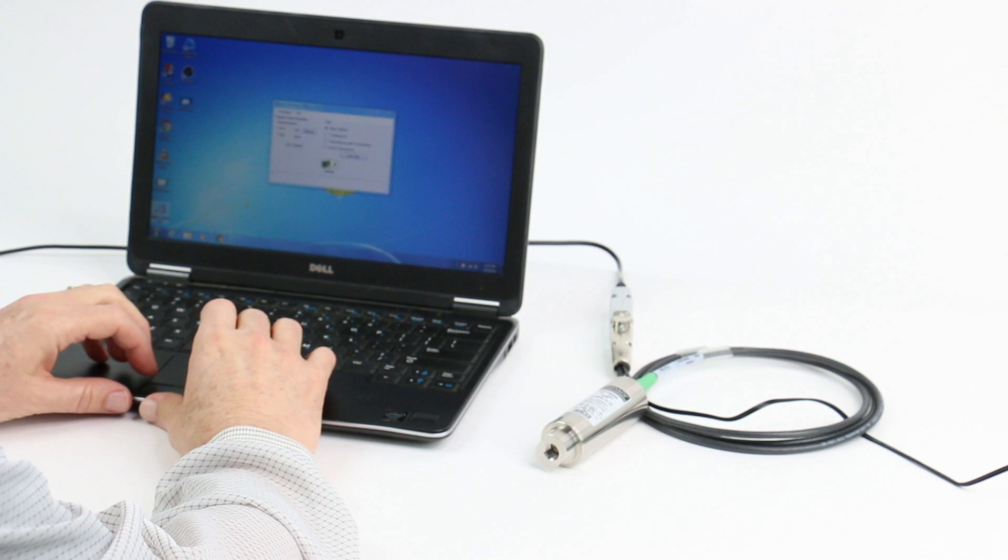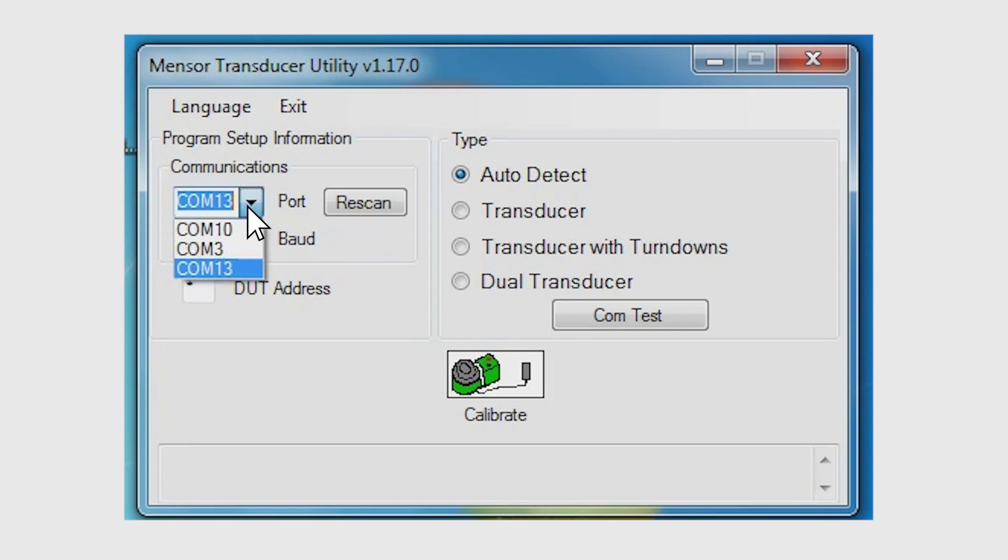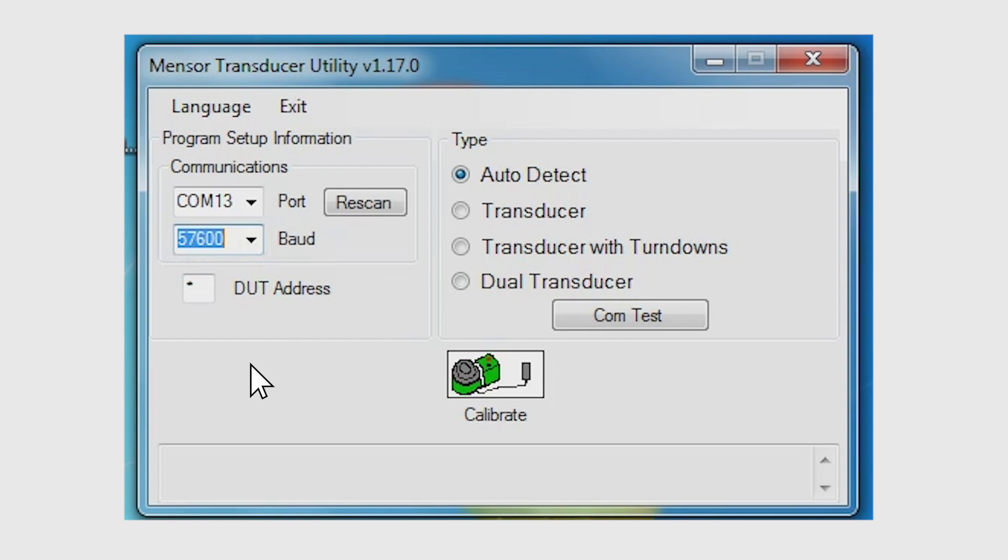After all connections are made, open the utility software and check to see if the transducer is communicating. The program will automatically find all available serial COM ports. Select the serial COM port connected to the transducer and the appropriate baud rate. The default baud rate is 57,600 baud.